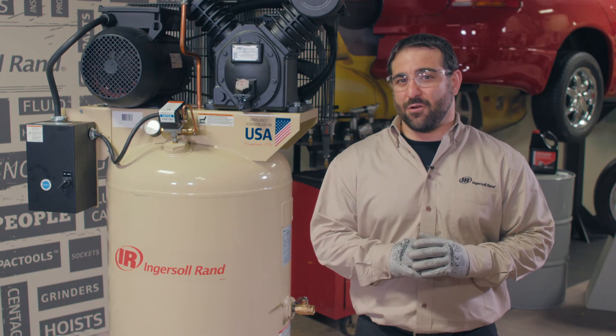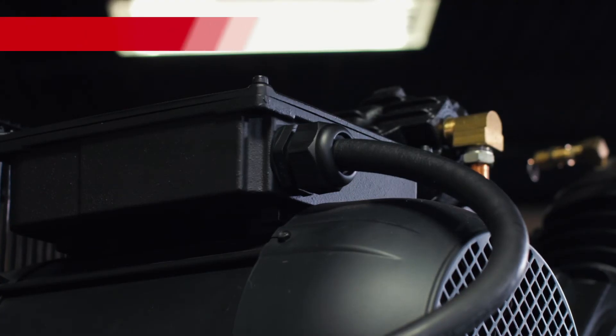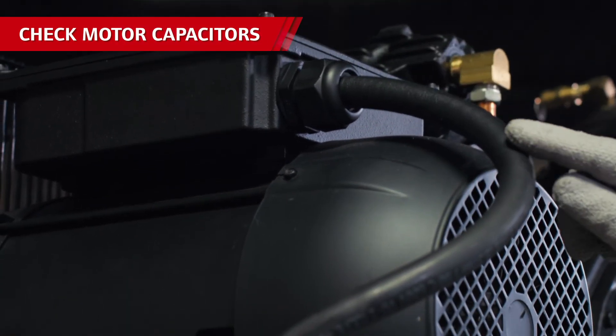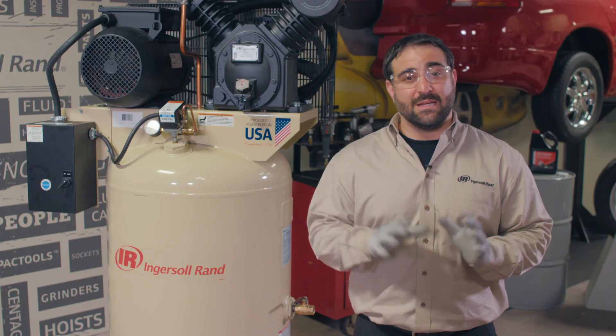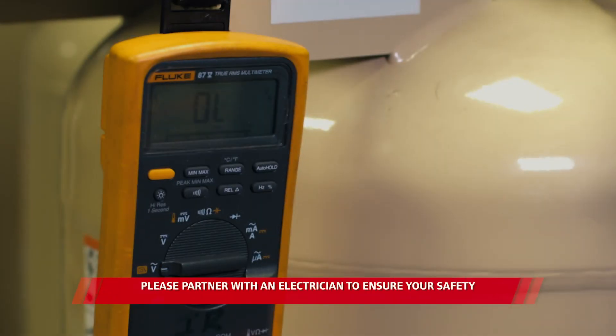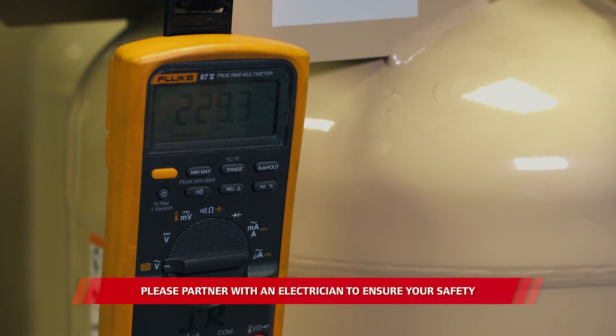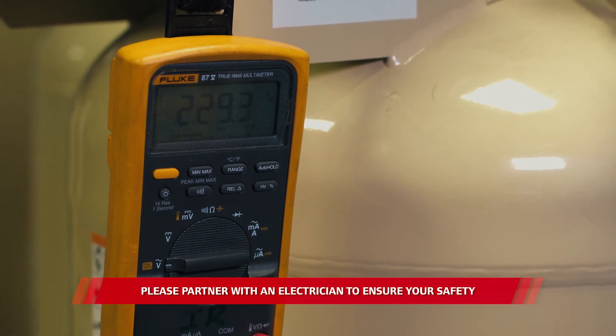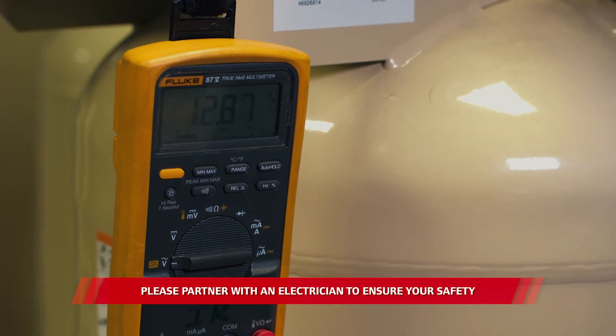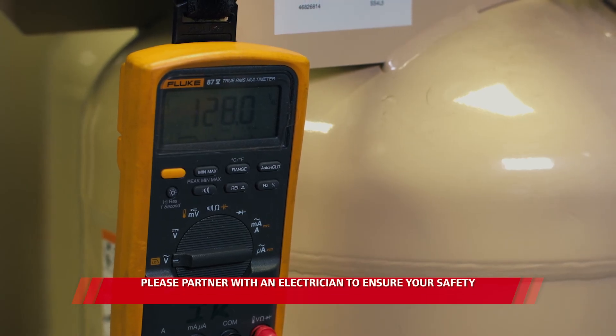Another thing to check if your compressor isn't building pressure correctly is the capacitors in the motor. If these aren't performing like they should, the motor isn't getting enough power to turn the pump at the proper speed, meaning it isn't compressing air efficiently. This can even cause the breaker to trip and the compressor won't start. A qualified electrical professional can perform a visual inspection of the capacitors for swelling, cracking, or leaking, and can check the capacitance of the parts using a digital multi-meter. This checks for micro-farad reading to make sure what's coming out matches the rating printed on the side. Capacitors with low readings or visible damage can easily be replaced in the motor.